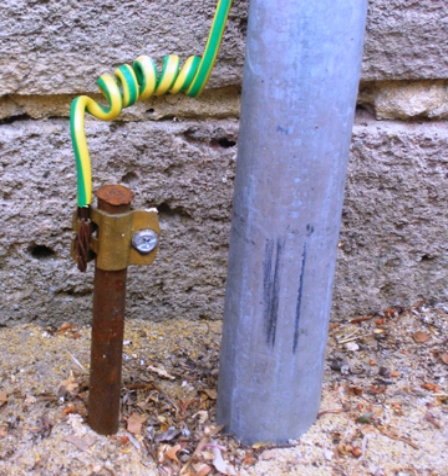Topic: Building wiring installations. Electrical power distribution systems are often connected to ground to limit the voltage that can appear on distribution circuits. A distribution system insulated from ground may attain a high potential due to transient voltages caused by arcing, static electricity, or accidental contact with higher potential circuits. A ground connection of the system dissipates such potentials and limits the rise in voltage of the grounded system.